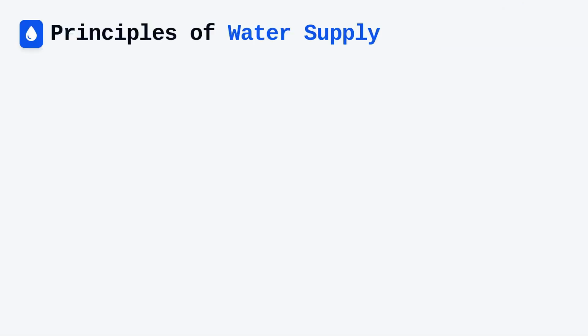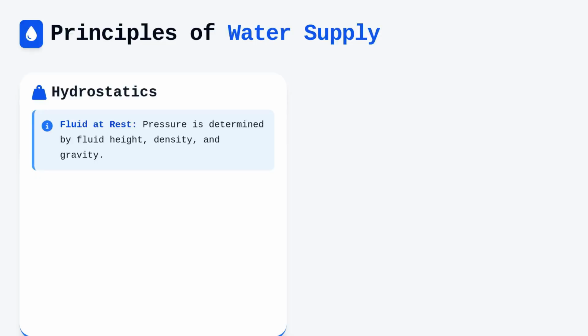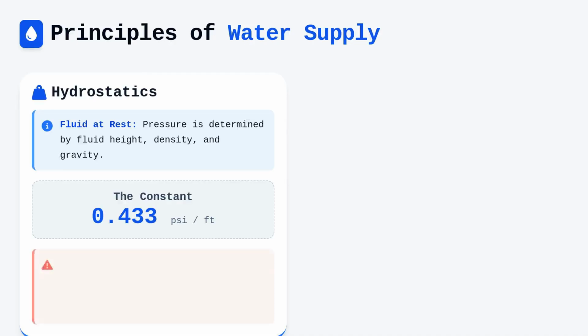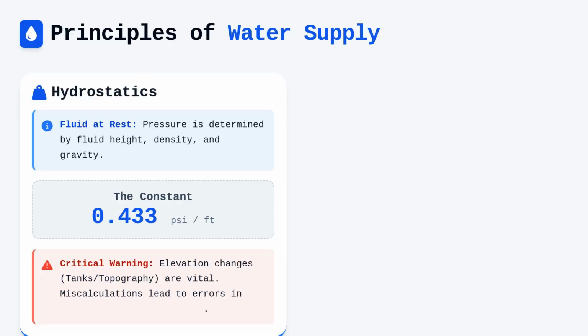To understand water supply, we begin with hydrostatics, which dictates the pressure exerted by a fluid at rest. For a vertical column of water, the pressure is determined by its height multiplied by the density of the fluid and the acceleration due to gravity, leading to the familiar constant of 0.433 pounds per square inch per foot of elevation. This is why elevation changes, whether caused by the height of an elevated storage tank or the topography of a municipal main, must be factored into every hydraulic calculation. If you miscalculate the effect of a 50-foot elevation gain, you have already guaranteed a significant error in your residual pressure analysis.